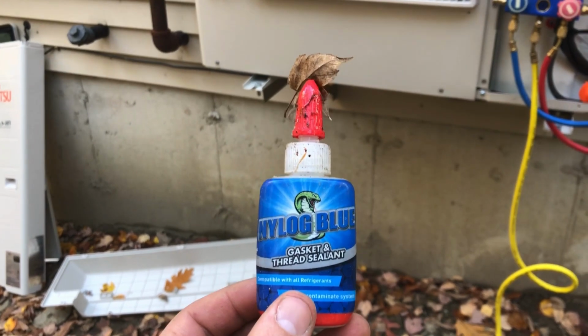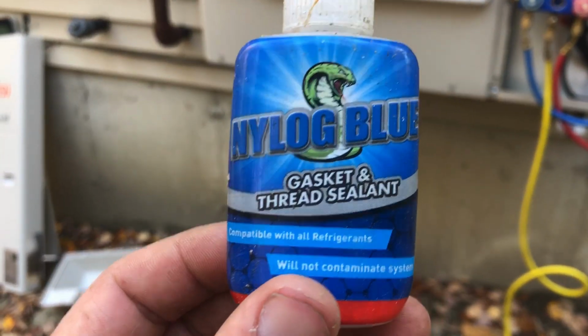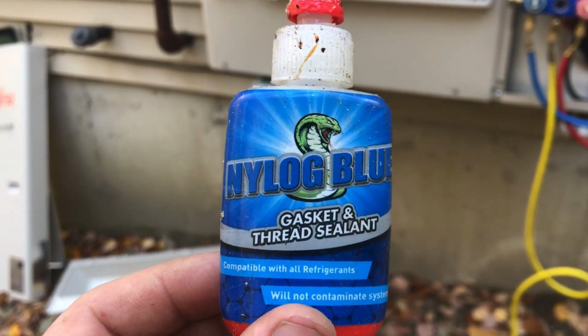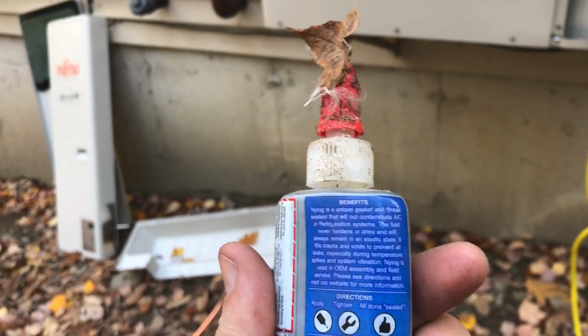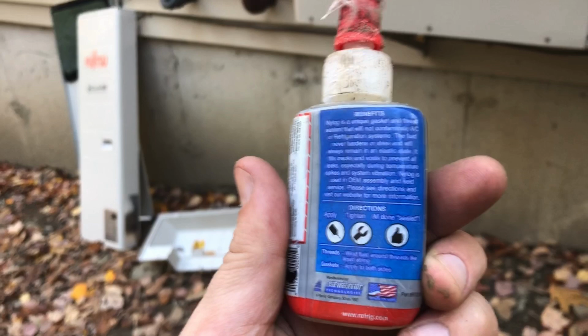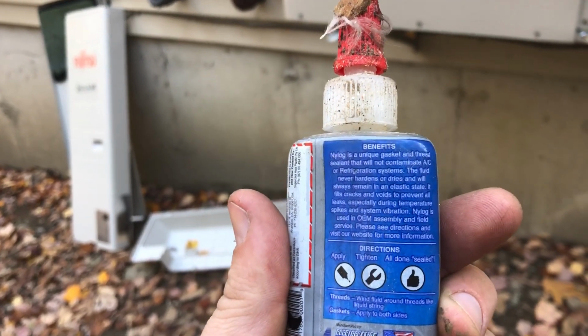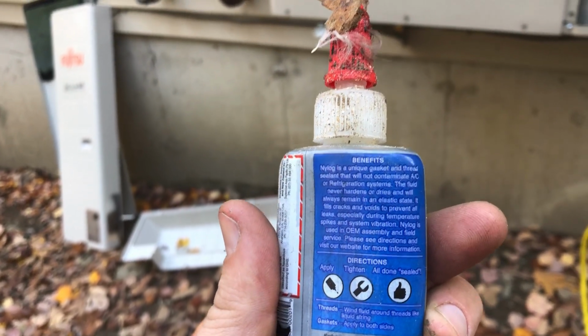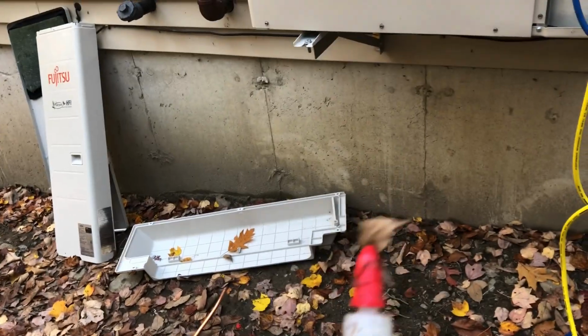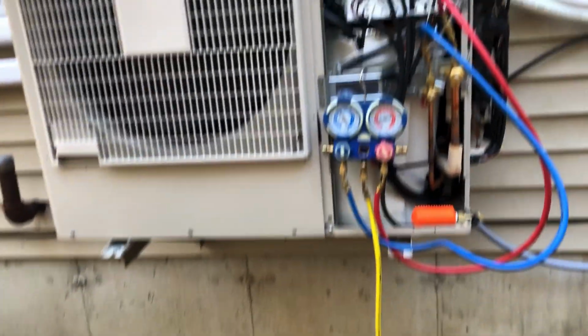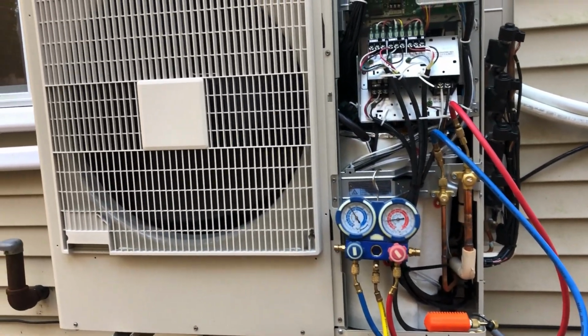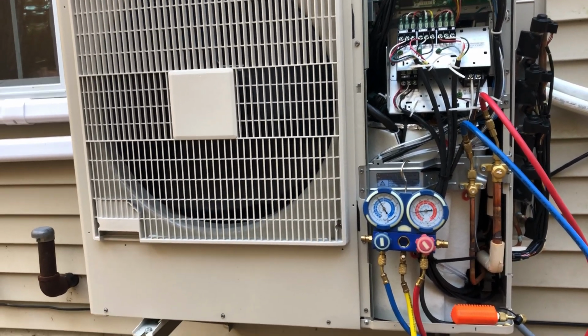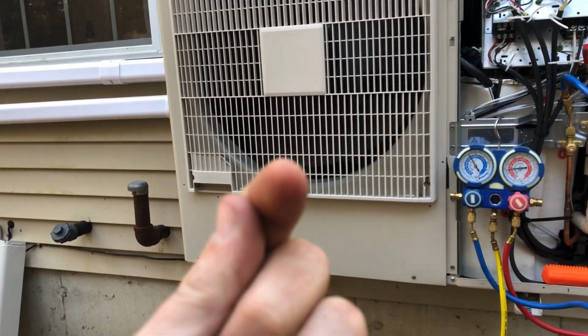Nylog Blue gasket and thread sealant - it's the only one compatible with all refrigerants. It will not contaminate it. Do not use Teflon or anything else to seal yours; this is the correct stuff to use. It will not contaminate 410A refrigerant, so it's very important.